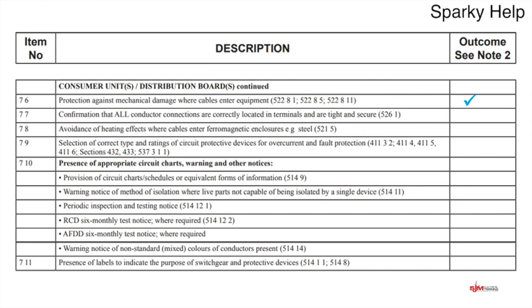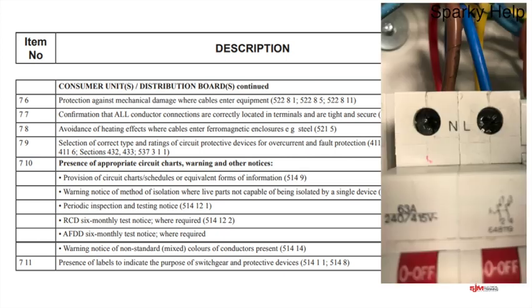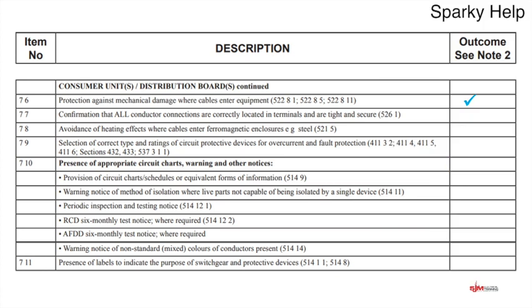Well, I think it's fairly obvious what that one would be, but you'd be looking for something like this. Hopefully what you can see there is that the line and neutral are round the wrong way. This is on the main switch, so therefore the polarity would be wrong. So it's just a visual thing, that's all we're doing. So we're going to have a look, going to pull it, touch it. Obviously we've probably installed it, so we'd probably know. Hopefully we wouldn't have installed it like this though. Hopefully if we recorrected that now, we would put a tick against it.